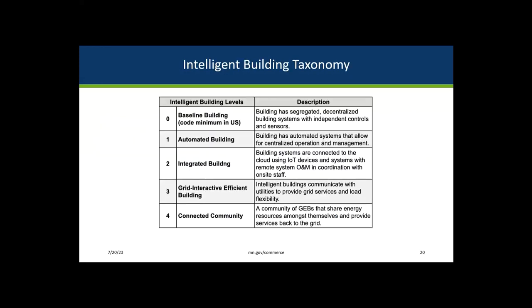To provide some guidance in the development of intelligent buildings, we've created an intelligent building taxonomy, which defines five levels in which intelligent buildings can be categorized. These are level zero, which is the baseline building, defined as complying with the US building codes. The building has segregated, decentralized building systems with independent controls and sensors. Level one is the automated building, which has automated systems that allow for centralized operation and management. Level two is the integrated building, where the building systems communicate with the cloud through IoT devices and systems to allow remote coordination with on-site building facilities and IT staff.